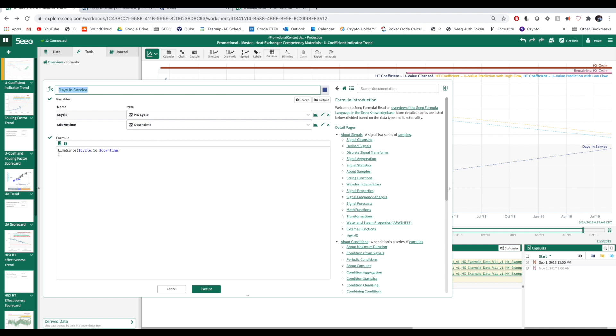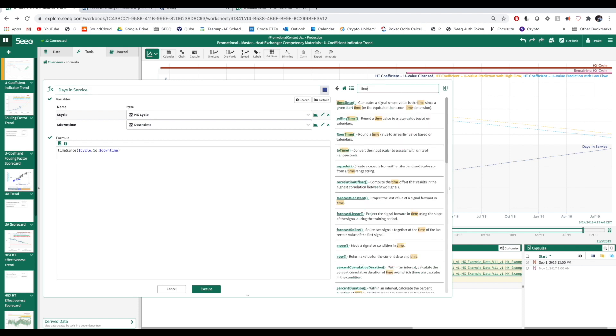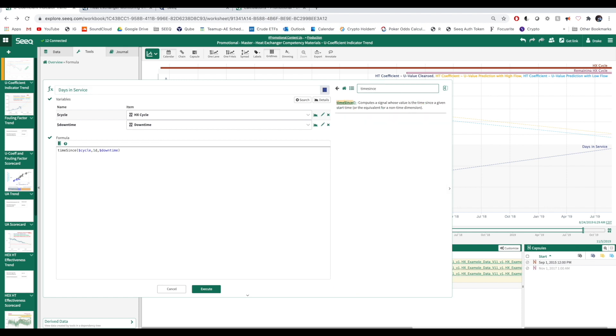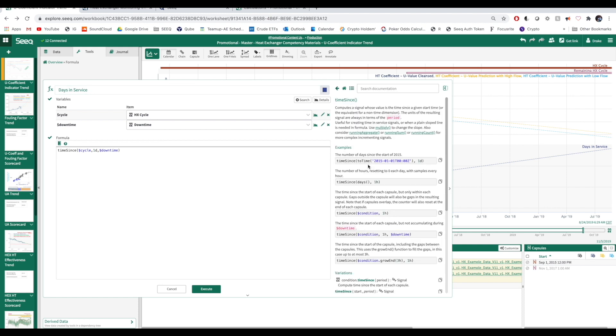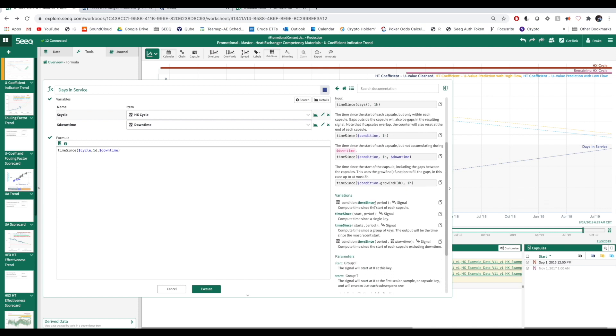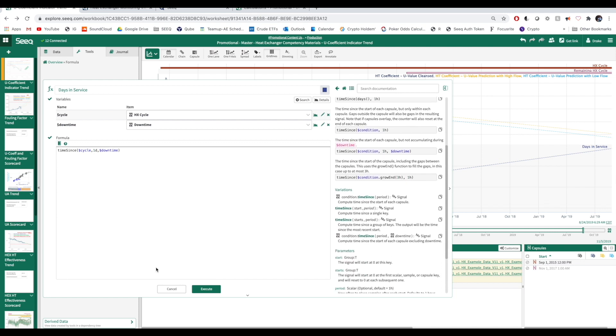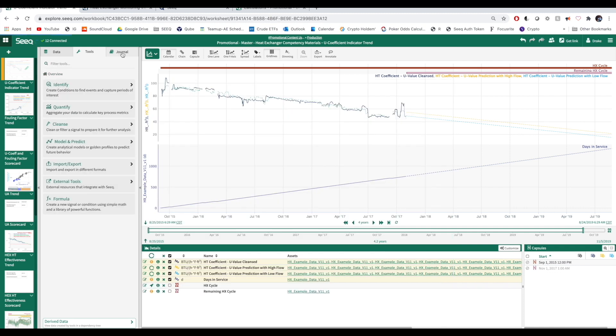To do this, let's hop over to the formula to take a look at the time since function. By specifying our heat exchanger cycle condition and one day, the signal increments by one each day. By specifying the downtime condition, we're telling it not to increment during those days.